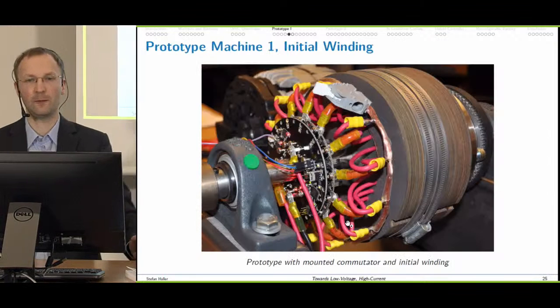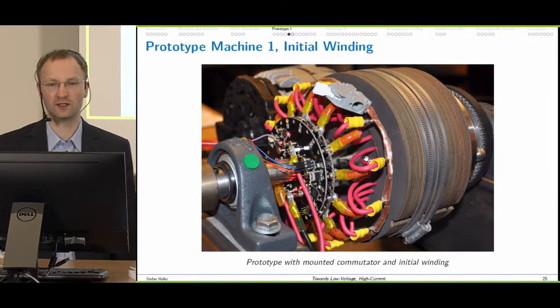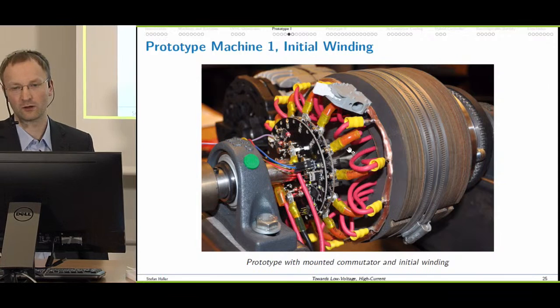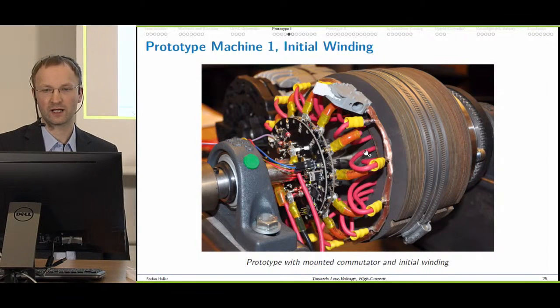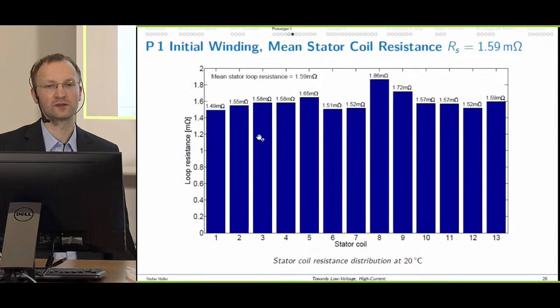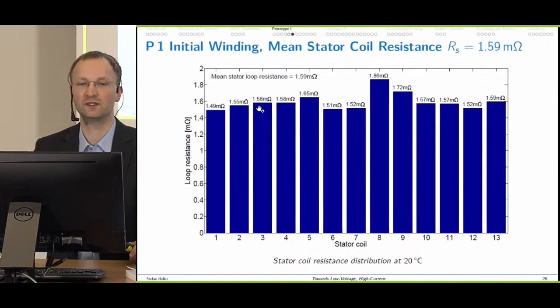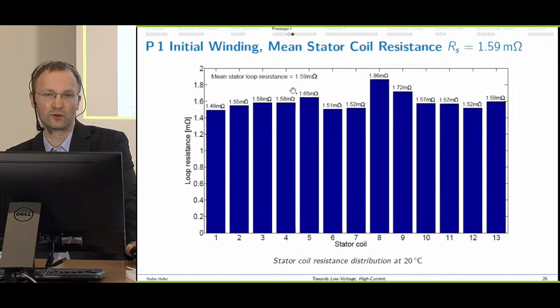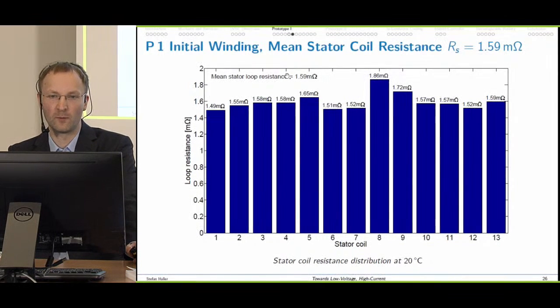Right, what we see here is the first time we had the machine assembled together, still with very long flexible cables and a very thin connection ring. As said, this is the first time we had it together. If we do the resistance measurements on that, we see a mean stator loop resistance of 1.6 milliohm and quite a large resistance variance.